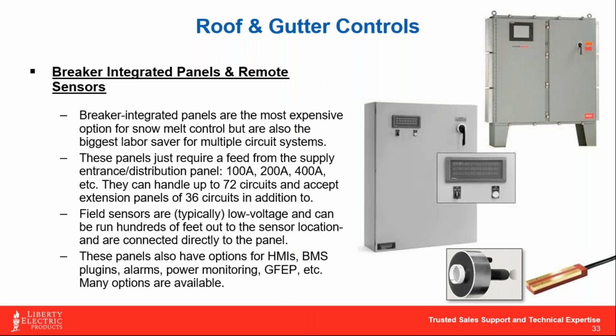So if you want to do that, you want to move into one of these larger breaker integrated panels. These ones are the ones that have all the options and come, as just mentioned, integrated fully with breakers. So these panels are, yes, the most expensive, but they're also the easiest to install. Instead of having to bring over, say, 4, 8, or 12 different circuits to a contactor relay panel where each of those has to get wired over, this panel distributes everything. So you would just bring in, say, a 100 amp or a 200 amp feed and make one power connection onto this panel, and then it does everything from there.